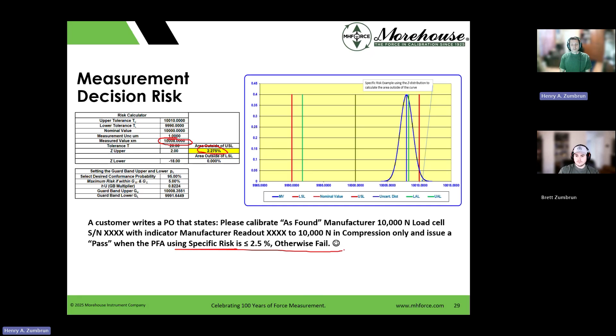This basically is telling us, I have a 10,000 Newton cell. My measured value is 10,008. Area outside the curve is 2.275%. Guess what? Their decision criteria is what here? It's less than or equal to 2.5%. We issue a pass, the customer agrees on the pass, and the risk is below that.